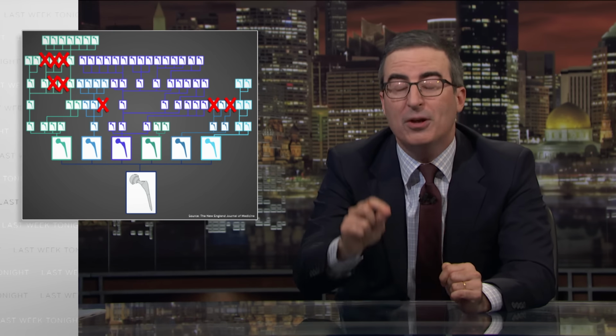Let me show you. In 2008, a company called DePuy received FDA clearance for a hip replacement based on its substantial equivalence to six previous devices, all of which were cleared because of their similarity to devices before that, and devices before that, and before that, all the way back to hips that were on the market in 1975. Incredibly, some of those devices had since been taken off the market by their manufacturers because of their high failure rates, but under FDA rules, DePuy could still use them as a basis for getting their hips cleared.